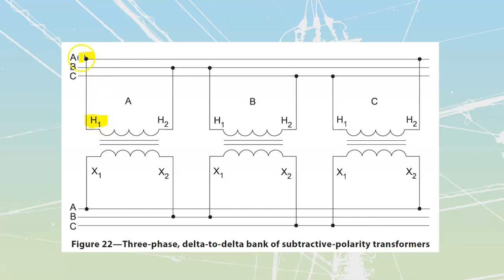Once again, the top side is done the exact same way: H1A, H1B, H1C, and then A goes over to B goes over to C goes back onto A. This is identical to what we had before, but now on the low voltage side we've got subtractive transformers - they're not crossing over the core of the transformer, therefore these are subtractives.